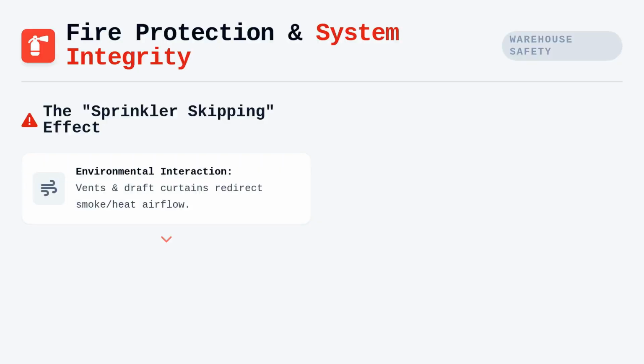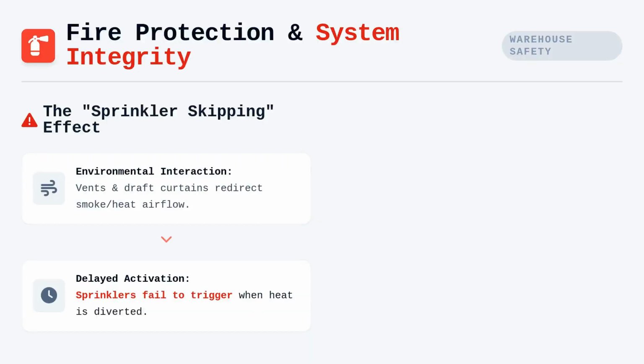Beyond the sprinklers themselves, we have to consider the environment's interaction with smoke and heat venting systems. A common failure mode in modern warehousing is the phenomenon of sprinkler skipping, which occurs when draft curtains or poorly placed vents redirect smoke away from sprinkler heads, delaying their activation. When sprinklers activate too late, the fire may have already reached a point where the local water density is insufficient for suppression.